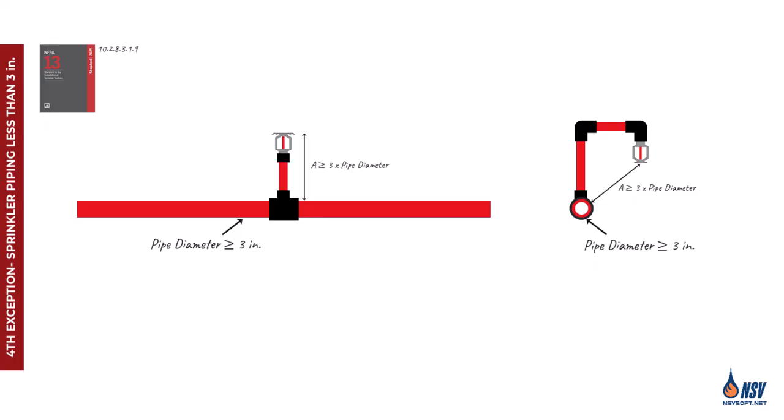For pipes three inches or larger, the rule does apply. These can block water discharge if too close to the deflector. To maintain proper clearance, three times the pipe's diameter, sprinklers must be installed on a sprig or arm-over, ensuring unobstructed coverage during a fire.